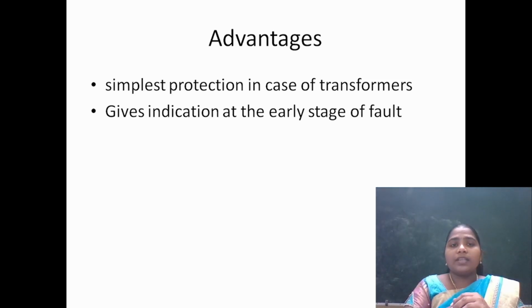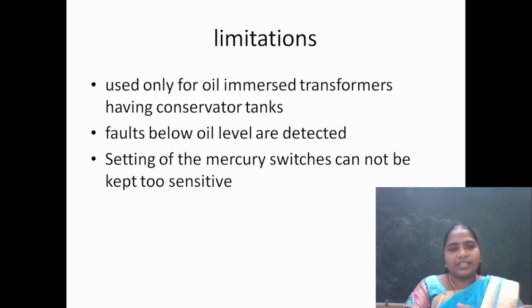The advantages of this Buchholz relay are that it is a simple protection for transformers, and it gives indication of the fault at the earliest level. Limitations: it is used only in oil immersed transformers where a conservator tank is present, and faults below the oil level can be detected. Faults above the oil level cannot be detected here. The setting of the mercury switches is not easy as they are too sensitive.